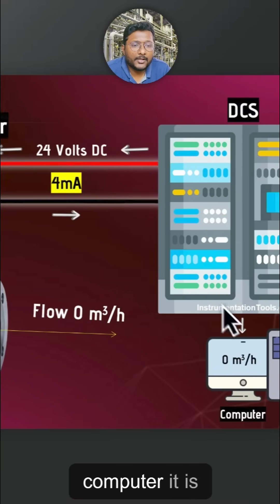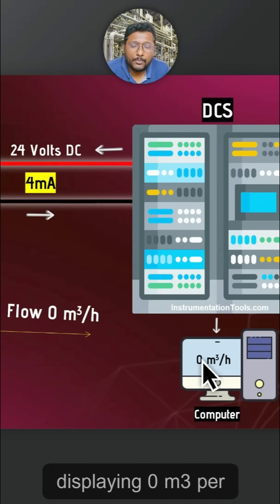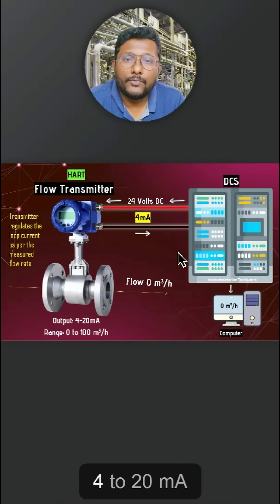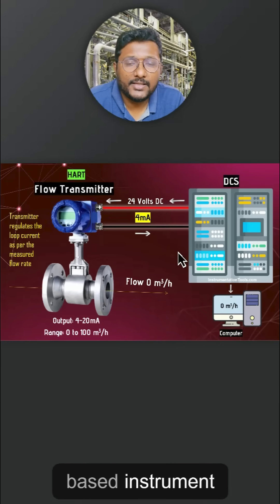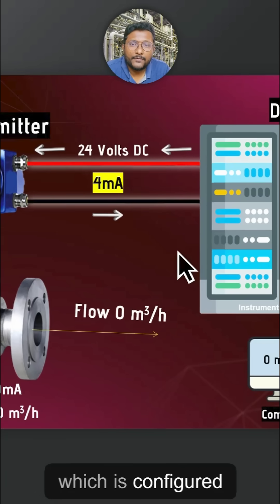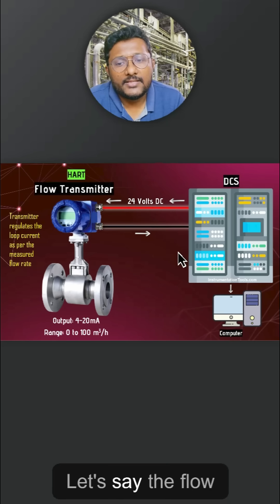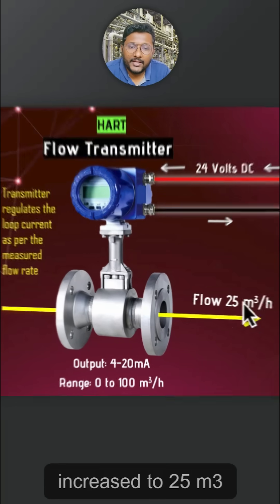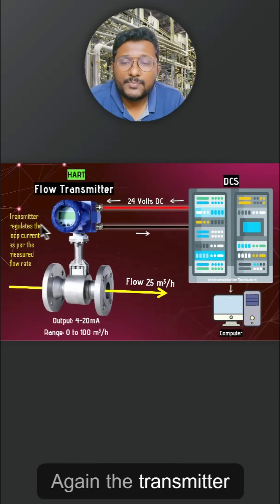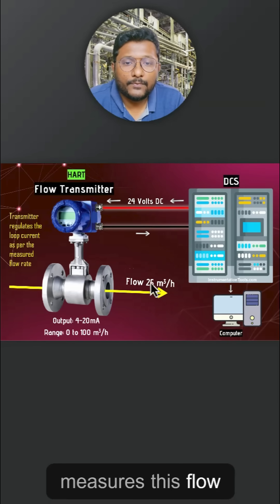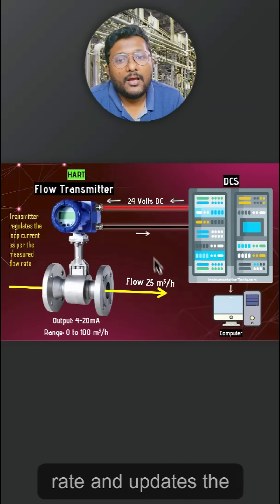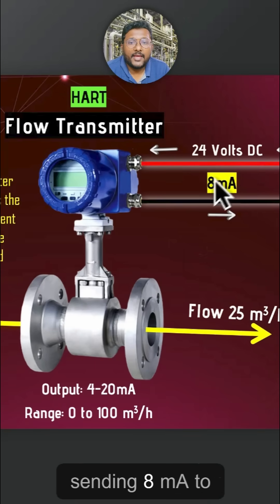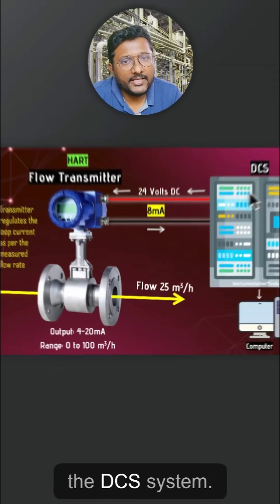The DCS measures this loop current and displays it to the operator, showing 0 m³ per hour on the operator computer. This is the basic concept for a 4 to 20 mA based instrument configured in a DCS system. Now let's say the flow increases to 25 m³ per hour — the transmitter measures this flow rate and updates the loop current accordingly, sending 8 mA to the DCS system.